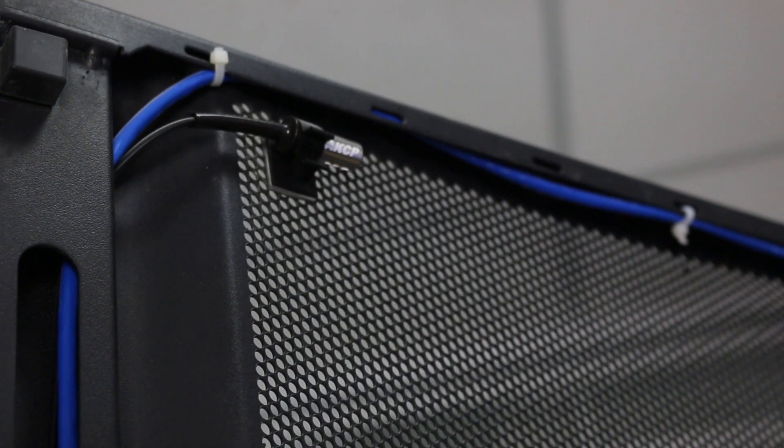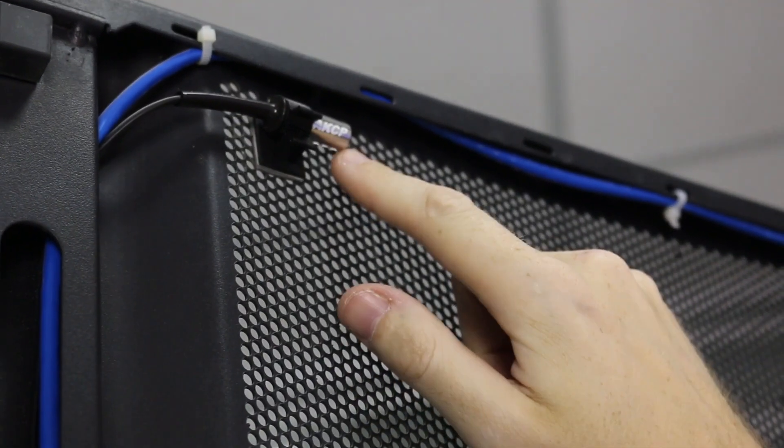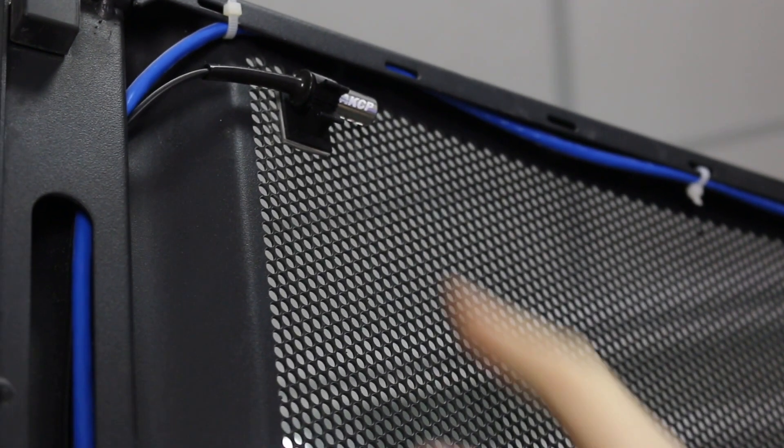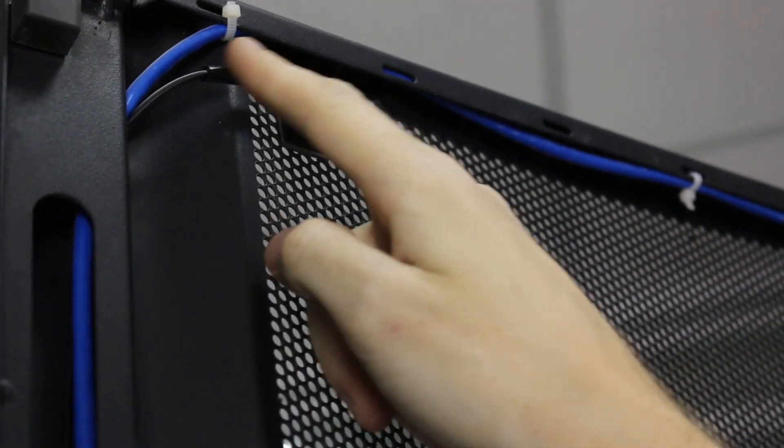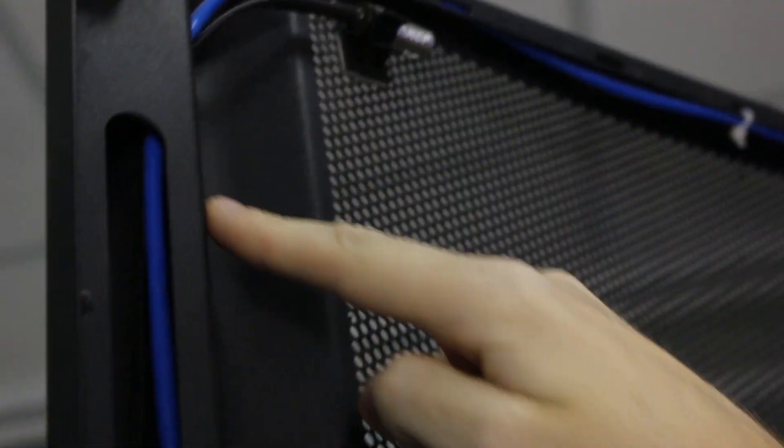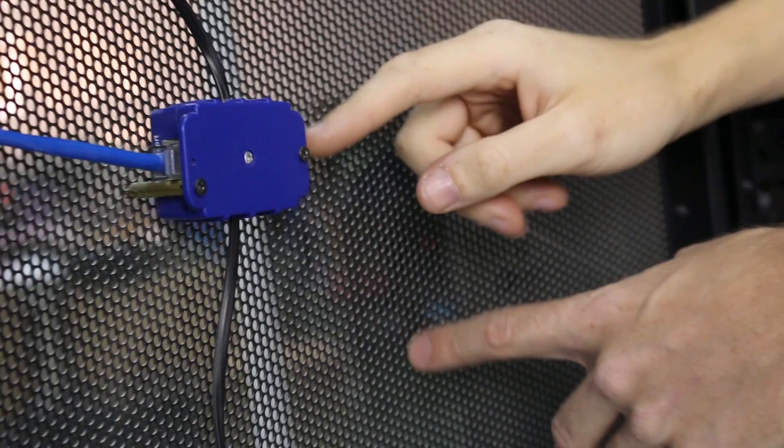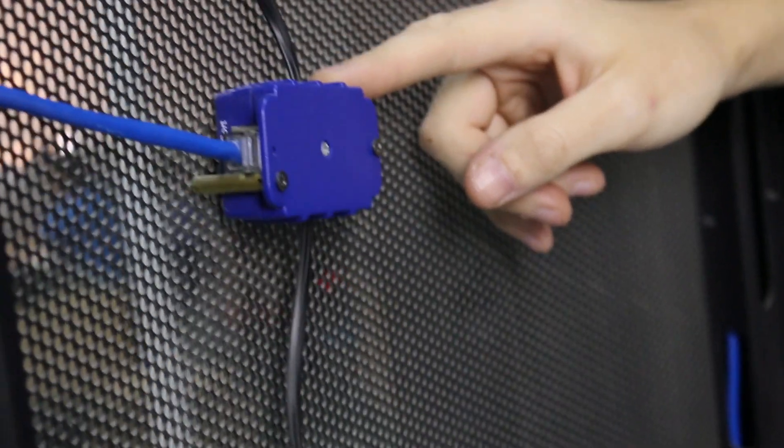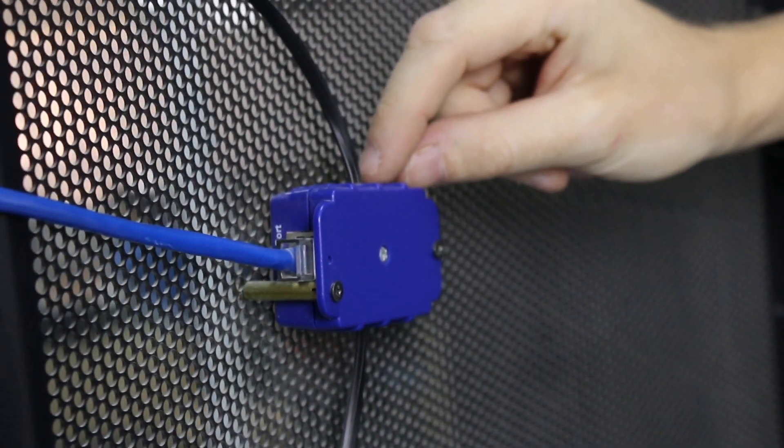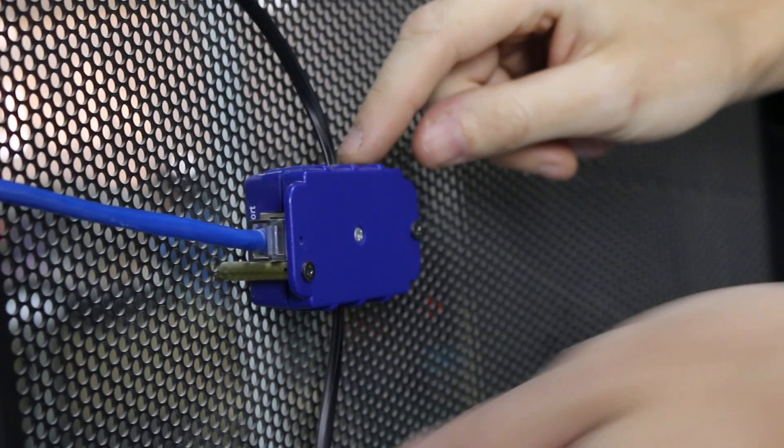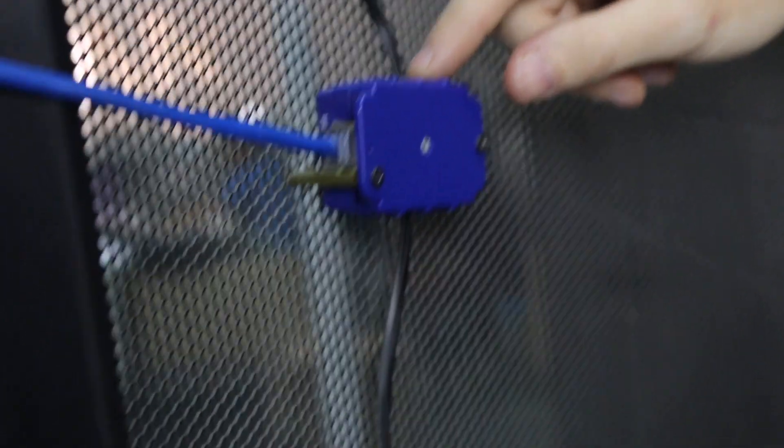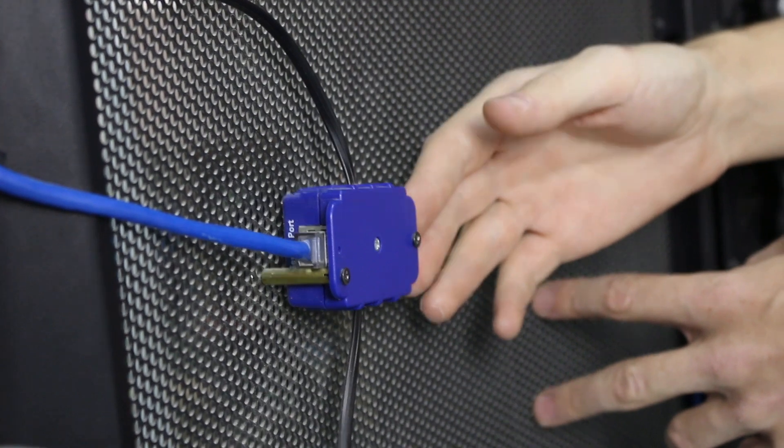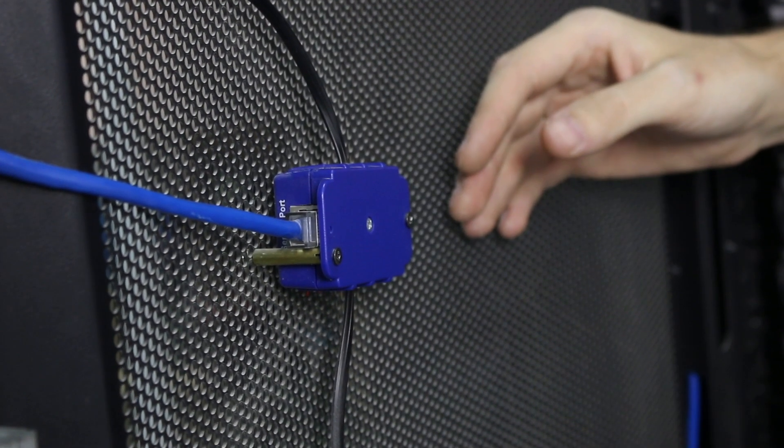At the top of the cabinet here you can see our temperature sensor on a wire running through the cable run on the front door. It comes down to our sensor box here where we have temperature and humidity. Following this cable down to the bottom, we have another temperature sensor installed at the base. This cabinet has a perforated front, so we're measuring the temperature of the air being drawn in by the servers through the front door.